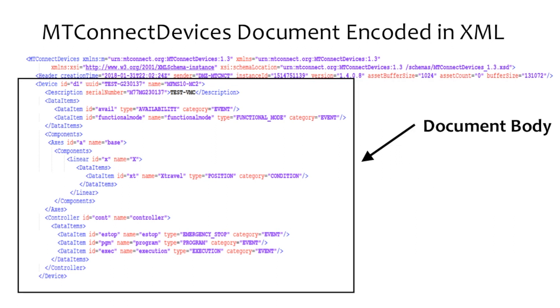The body section of the document contains the data and other information requested by the client software application, organized based on semantic data models defined in the MT-Connect standard. If the request was for metadata describing one or multiple pieces of equipment and the data that can be reported by that equipment, then the response document will be organized based on the semantic data model defined in part 2 of the standard, the Device's Information Model. The resulting response document is called the MT-Connect Devices Response Document.